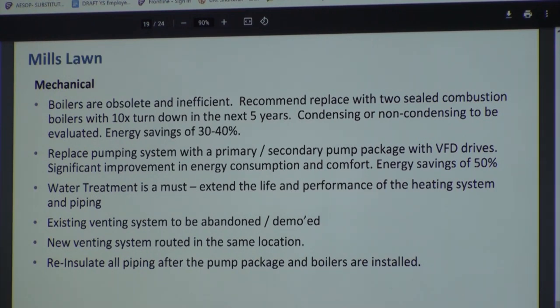So, boilers in the middle school are obsolete and inefficient, but they're not horrible. I would say those units are in better shape than the Kelly Patterson units. If you replace those in the next 5 or so years, you're okay. Those have sealed combustion, so you're getting air from the outside. They have an inlet, so you're not using building air for combustion. So those are better units. They have a turn down, and they still make those units, so if you lose one, you could replace it with a very similar, if not exact, same model as what's there.